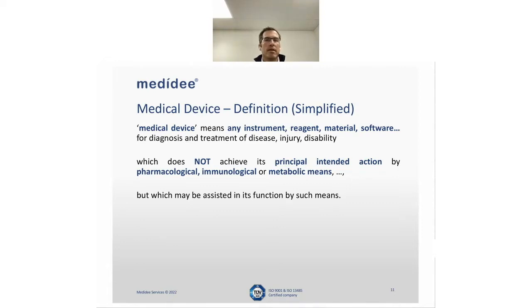What is quite interesting in that field is the whole world of what we call borderline medical devices, which can be classified in one category or another depending on the device. When you look at software, what is really important to take into consideration in terms of the definition is this: maybe you will consider your software a non-medical device because you developed it to do a specific action, to support the user to manage some data or to calculate some parameters and so on. And then the way this software interacts with other objects will influence its own classification.